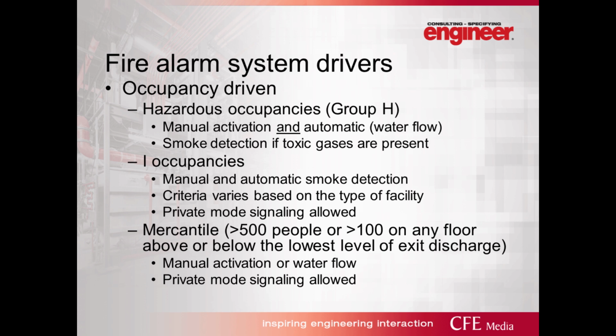Hazardous occupancies, Group H. Group H is one occupancy that requires manual activation and automatic. Manual pull boxes are required in Group H occupancies. We have smoke detection required if toxic gases are being utilized in that facility.